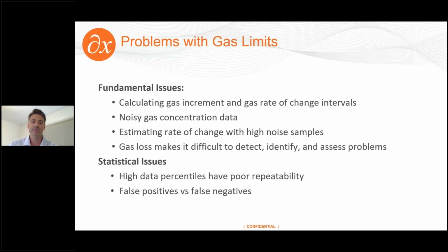This noise makes it difficult for interpretation. And gas rates of change are based upon consecutive high noise samples. This is unreliable and prone to false alarms. And gas loss from the transformer or sample makes it difficult to detect, identify, and assess problems.